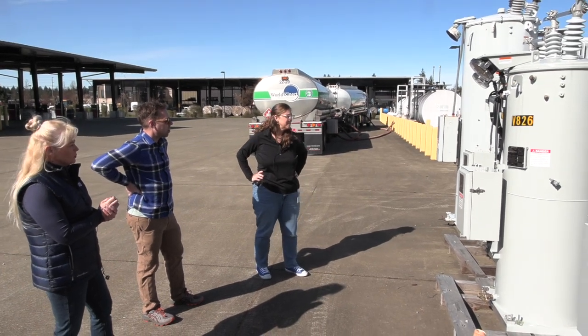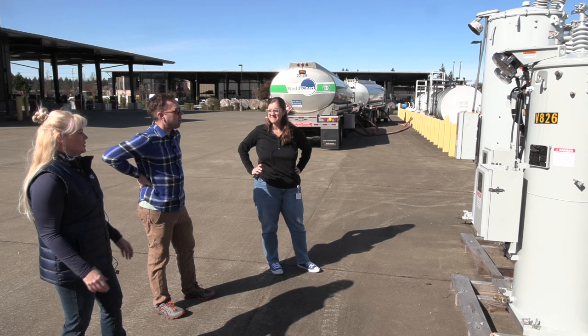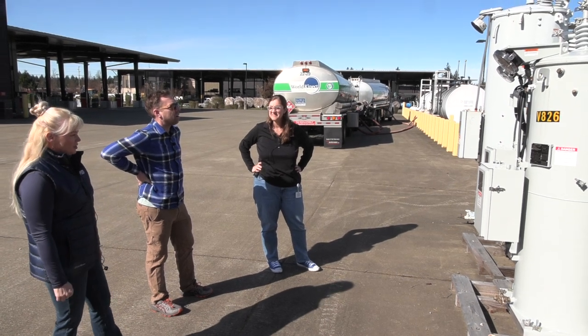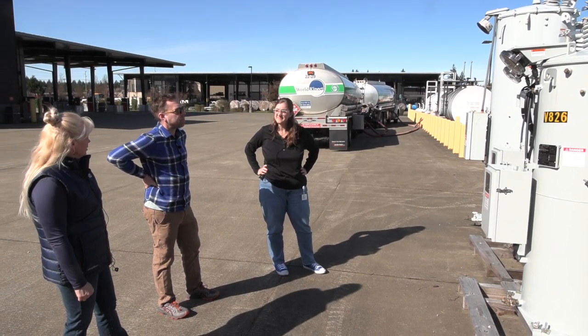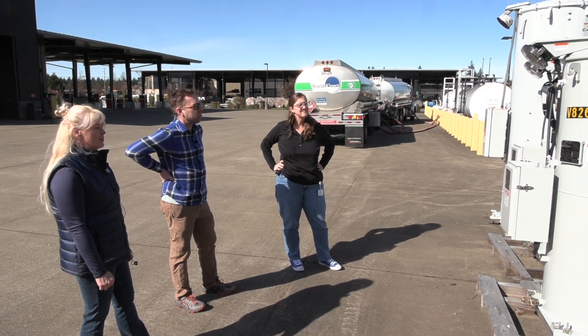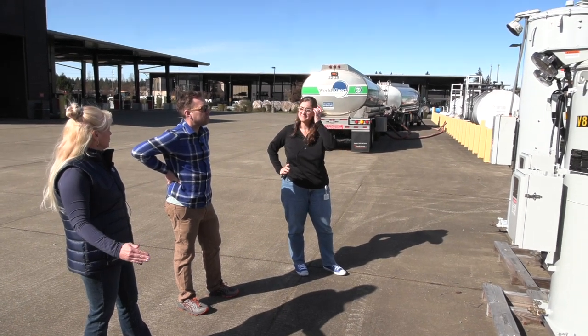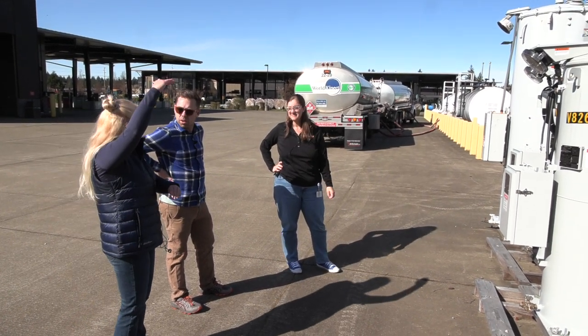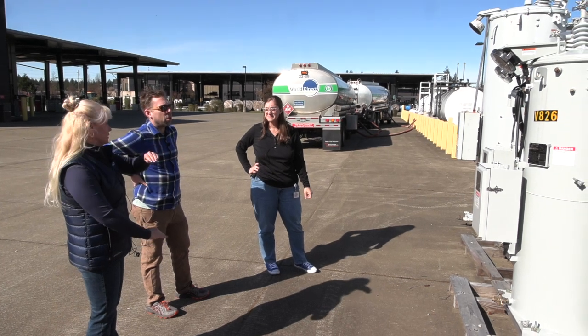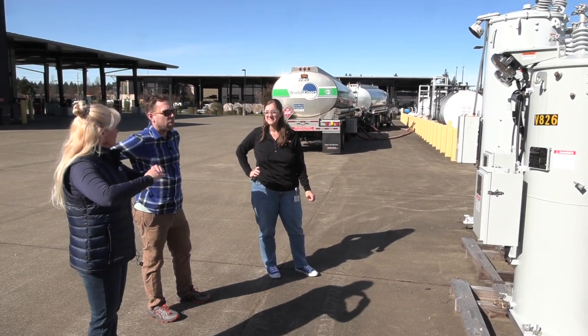Amps times volts equals watts. What these will do is deal with the voltage side of things. So if we have an incoming voltage that is too low, these things can tap and actually increase the voltage. They can go up 10% or go down 10%, if needed, depending on the incoming voltage range.